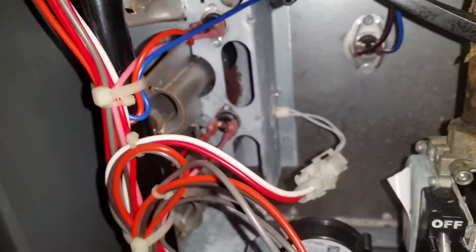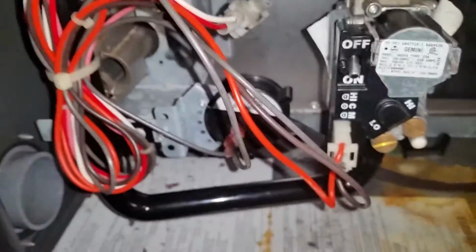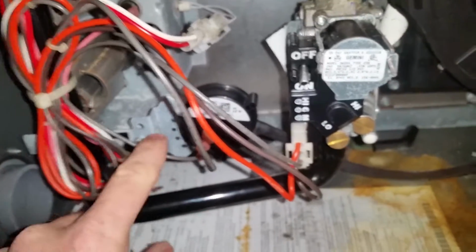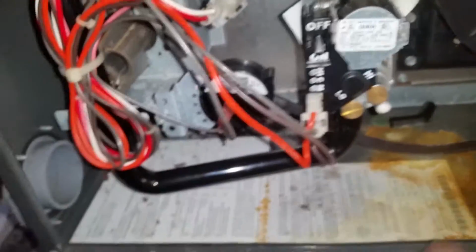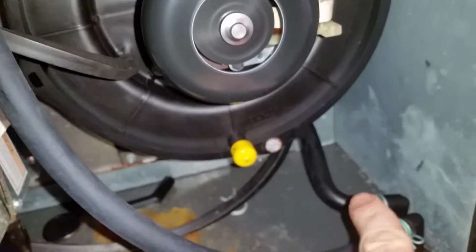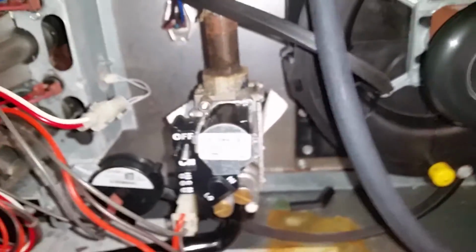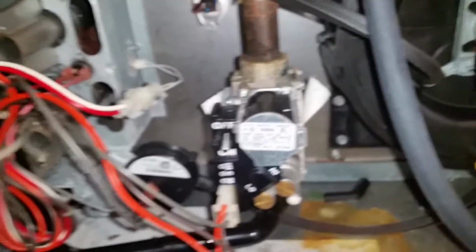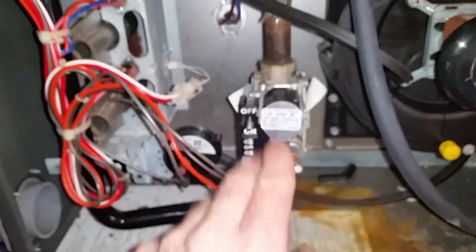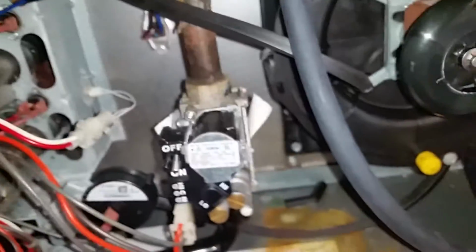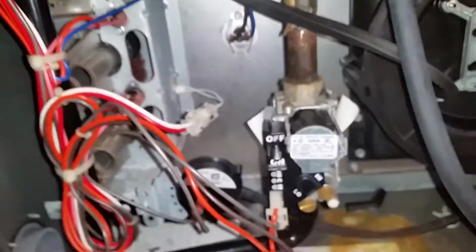And then we have our lower pressure switch, which is tied to the gas valve, because this one is reading the heat exchanger. This is reading primarily the condenser coil area of the heat exchanger. And so it did not allow the gas valve to open because it's indicating that we're not getting a proper draft on our heat exchanger.